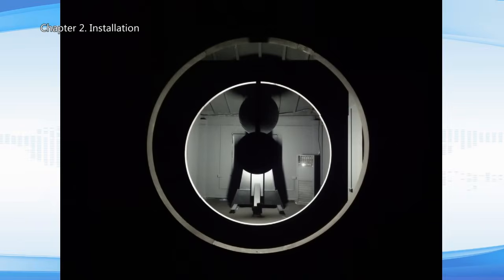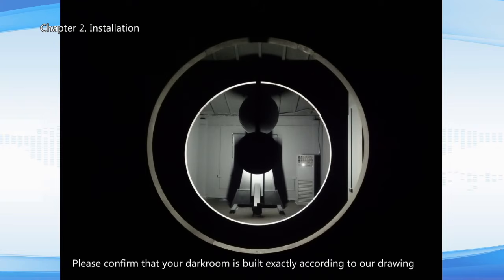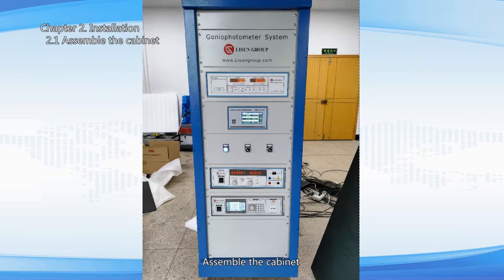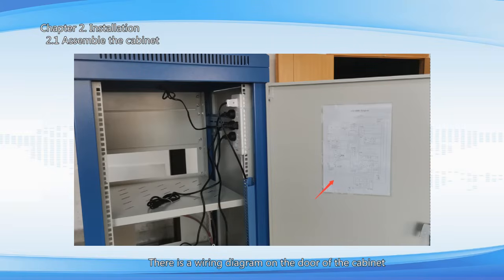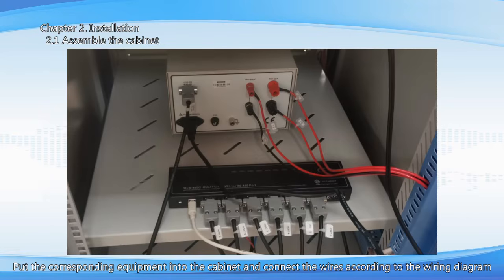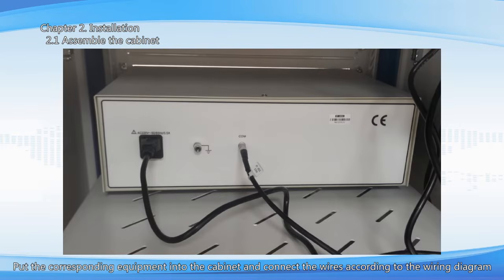Chapter 2. Installation. Please confirm that your darkroom is built exactly according to our drawing. Assemble the cabinet. There is a wiring diagram on the door of the cabinet. Put the corresponding equipment into the cabinet and connect the wires according to the wiring diagram.